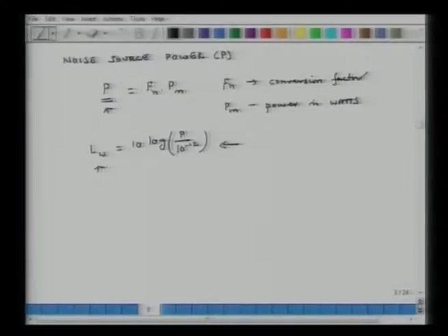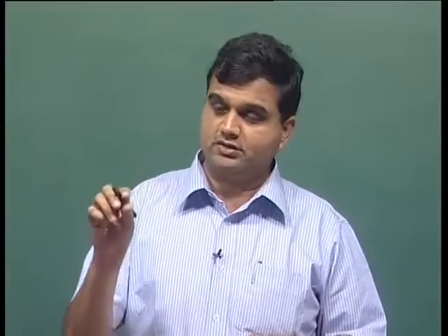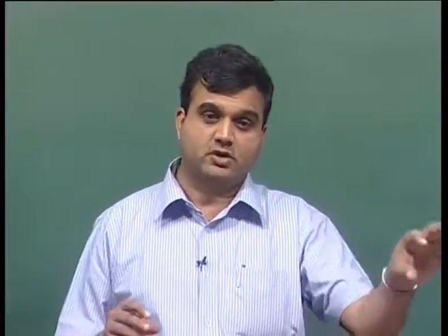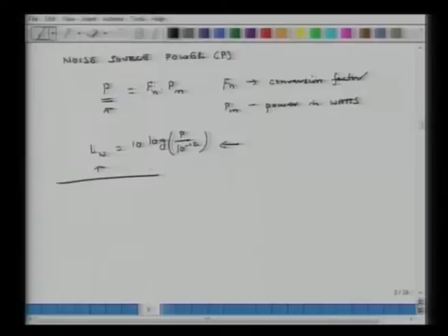So based on this, if you know that you have 20 pieces of machinery in this whole setup, or 20 different sound emitting components, and for each component you can figure out LW1, LW2, and so on, then what I am measuring is a noise spectrum which has certain amplitude at different frequencies. Based on that, you can map how much noise is coming from which particular component. It gives you some coarse understanding of that. Okay, so with this brief discussion, we will talk about noise signatures.